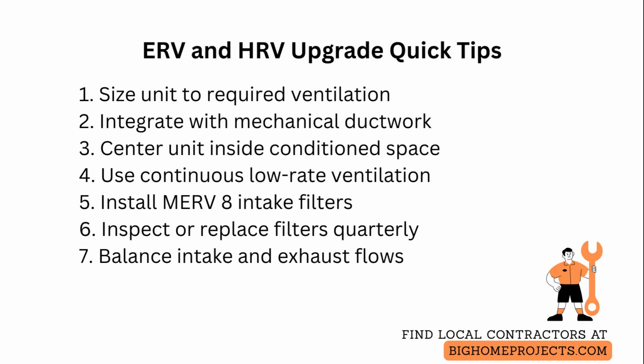Add minimum efficiency reporting value rated filters of at least MERV 8 on the outdoor intake and MERV 6 on the supply side if the system manufacturer requires lower resistance, and check pressure drop charts to avoid overloading the fan. Inspect or replace filters on a regular cadence, such as every 3 months and more often in dusty climates.